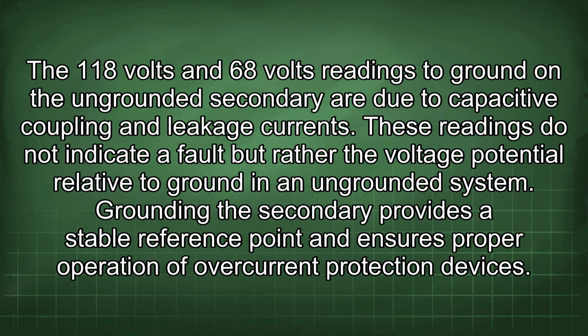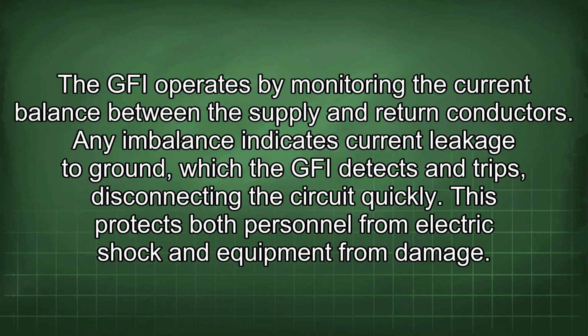The 118 volts and 68 volts readings to ground in the ungrounded secondary are due to capacitive coupling and leakage currents. These readings do not indicate a fault, but rather the voltage potential relative to ground in an ungrounded system. Grounding the secondary provides a stable reference point and ensures proper operation of overcurrent protection devices. The GFI operates by monitoring the current balance between the supply and return conductors. Any imbalance indicates current leakage to ground, which the GFI detects and trips, disconnecting the circuit quickly. This protects both personnel from electric shock and equipment from damage.